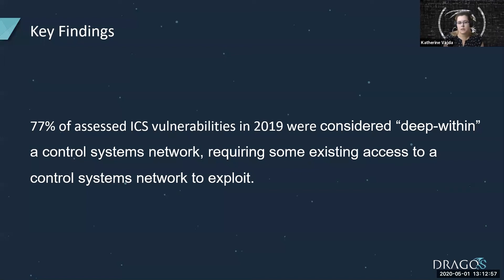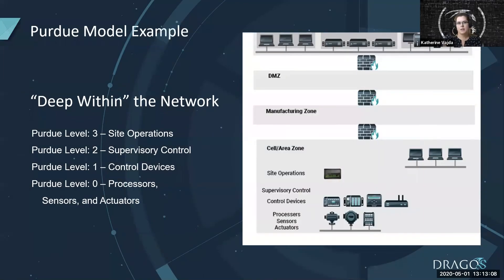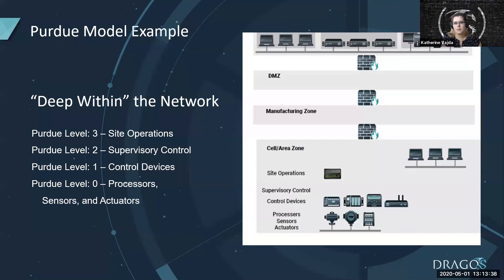77% of assessed vulnerabilities were considered deep within a control systems network, requiring some existing access to a control systems network to exploit. This means we've marked them as either Purdue Model 3, 2, 1, or 0. These could be devices such as Modicon 7, SIPROTEC relays, ABB Relion 650s, PLCs, industrial switches, or wireless routers. It could be licensing software like Advantech, Diag Anywhere Servers, FlexNet Publisher, Plant Connect, or SciTech. If these devices aren't deep within your network and are accessible from enterprise, DMZ, or even the internet, then you have bigger problems beyond the vulnerabilities. Several of these devices — just being able to route network packets to them alone — is an increased risk. Depending on your maturity model, your network might not be architected in the way that we're describing when we say deep in the network.